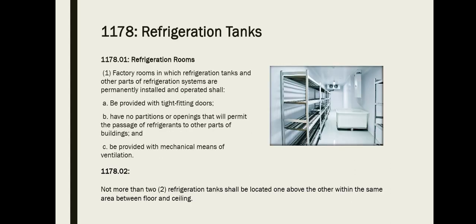Next is Rule 1178, refrigeration tanks. Factory rooms in which refrigeration tanks and other parts of the refrigeration system are permanently installed and operated shall A, be provided with tight fitting doors. B, have no partitions or openings that will permit the passage of refrigerants to other parts of buildings. And C, be provided with mechanical means of ventilation.